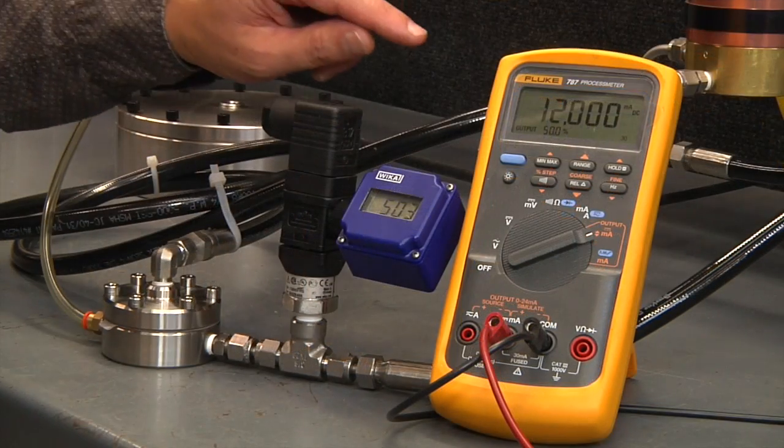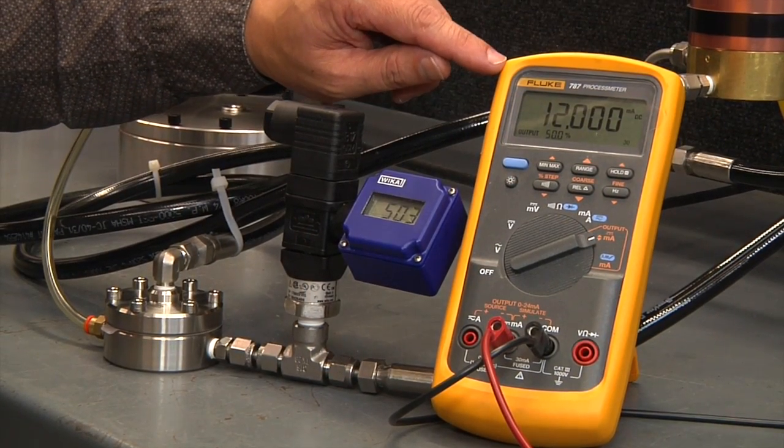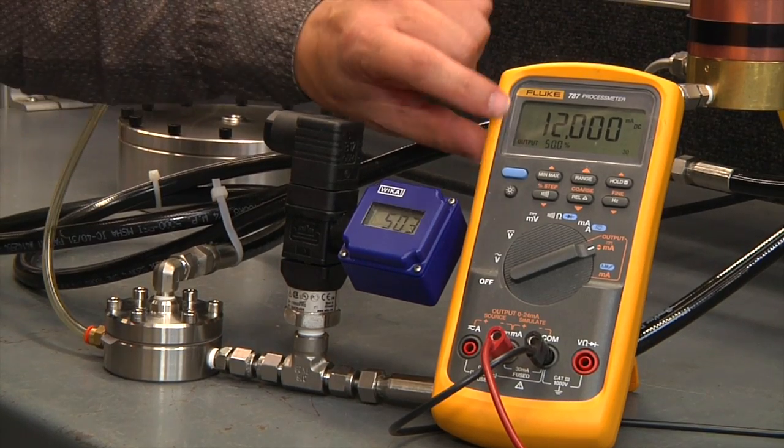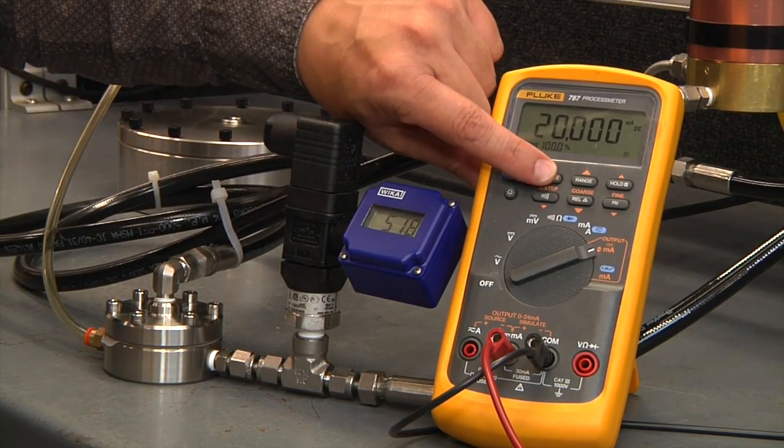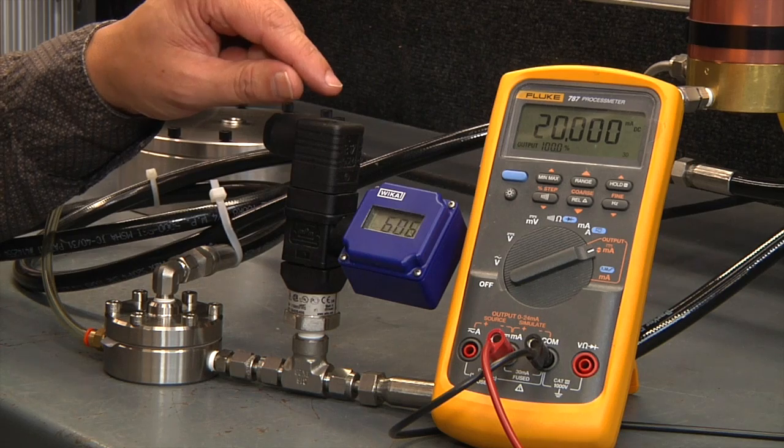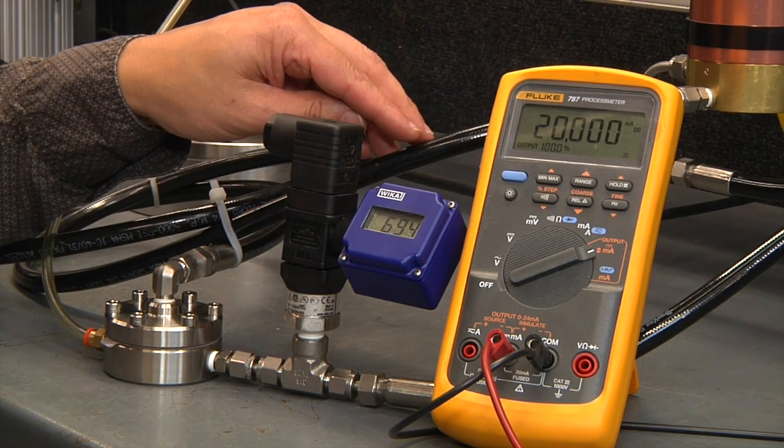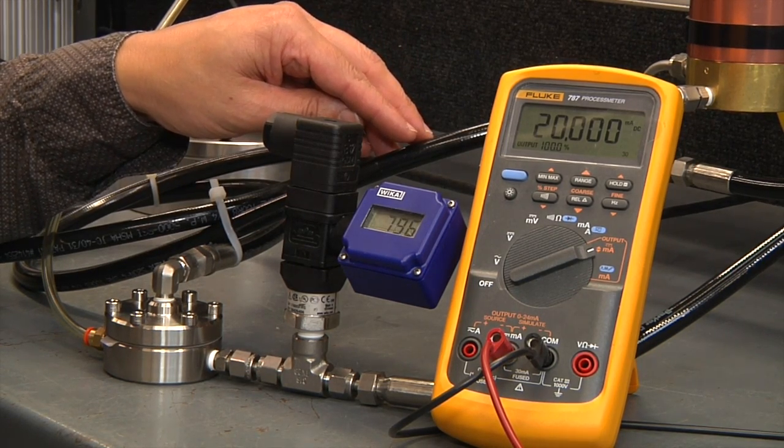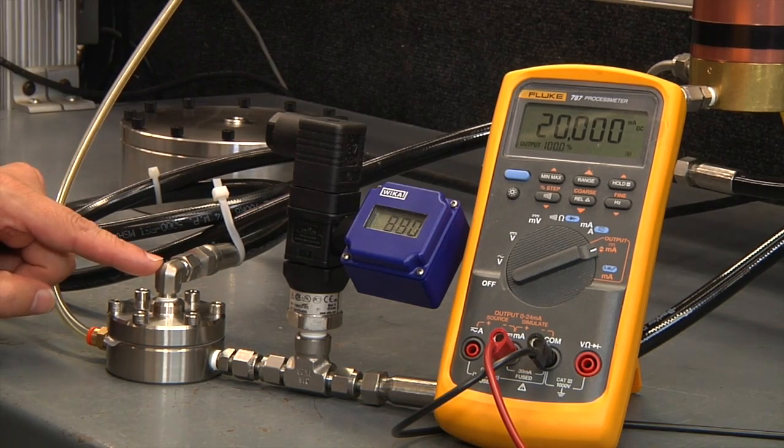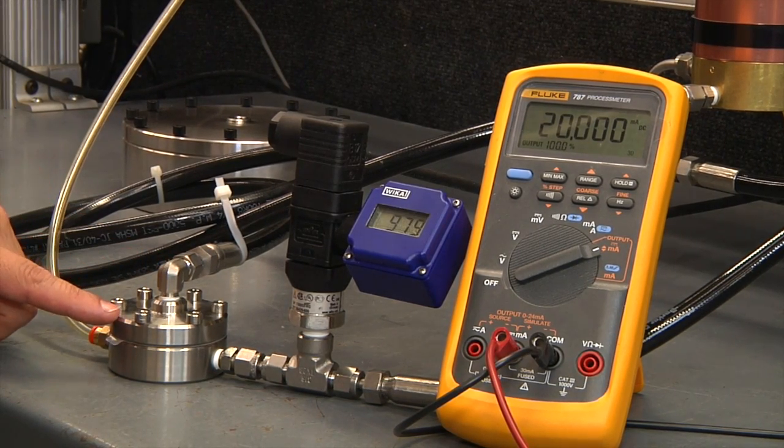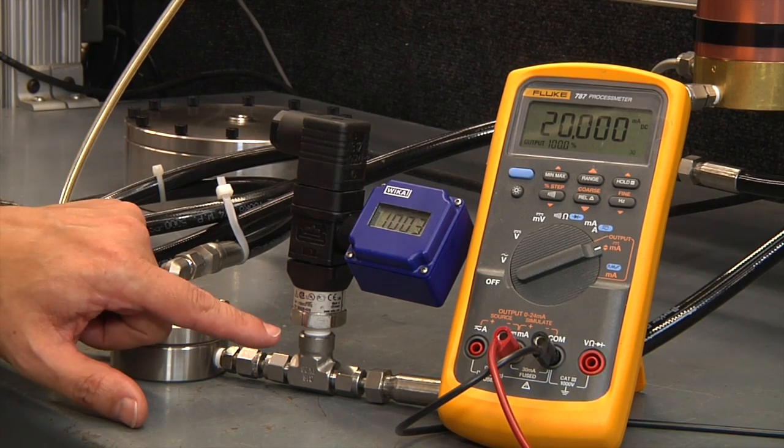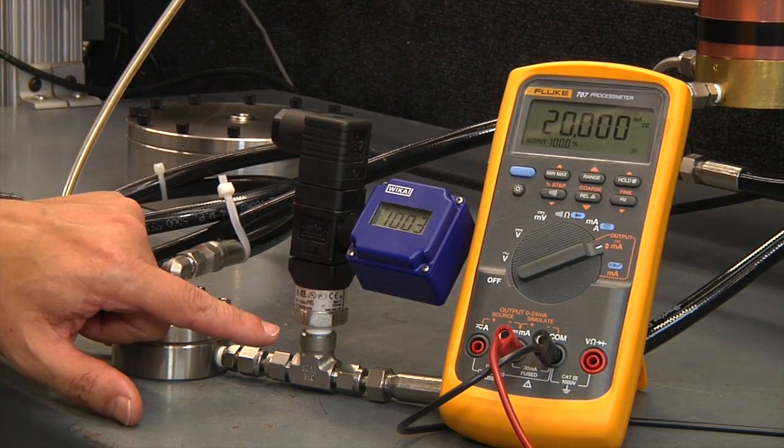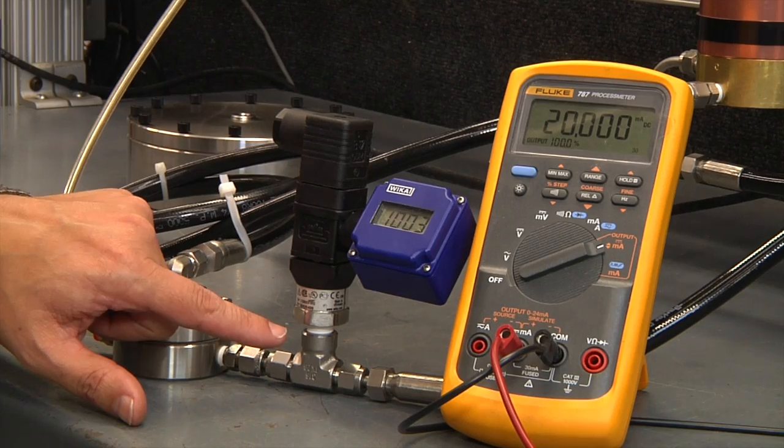Now we'll increase the command signal from 12 milliamp to 20 milliamp, which represents 100% command and for this particular unit represents 1000 PSI. So we'll provide 1000 PSI pilot to the LF Series back pressure regulator, which should control 1000 PSI of back pressure in your system.